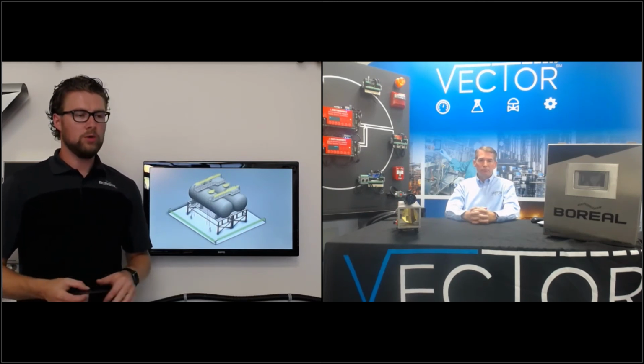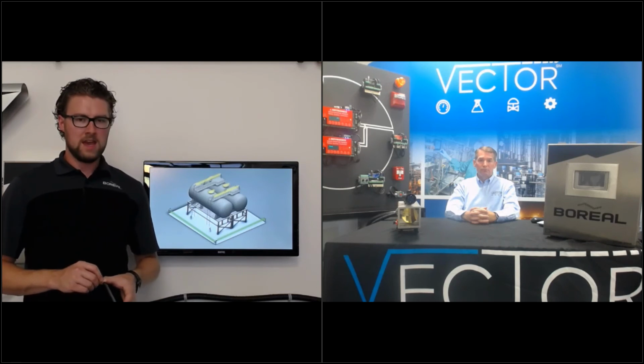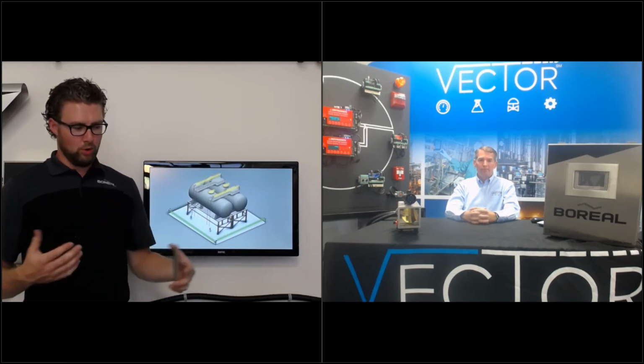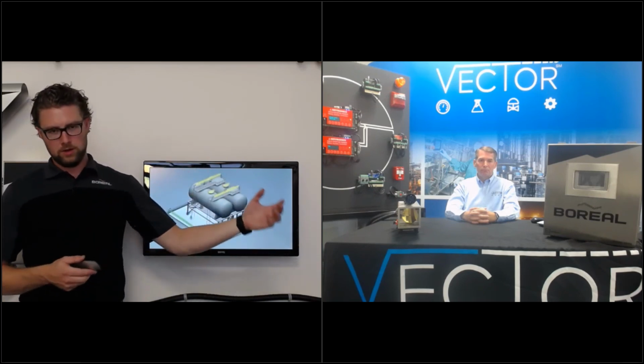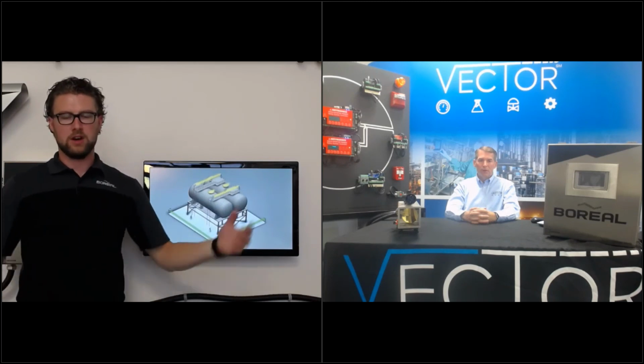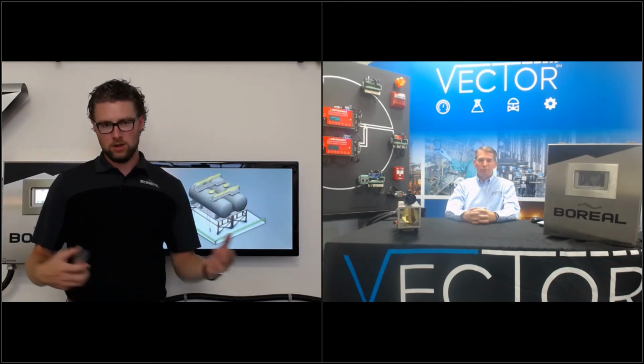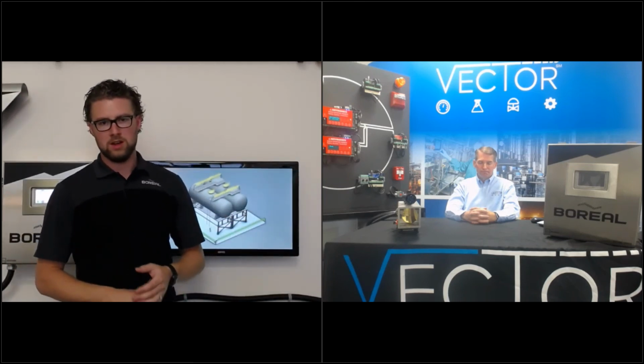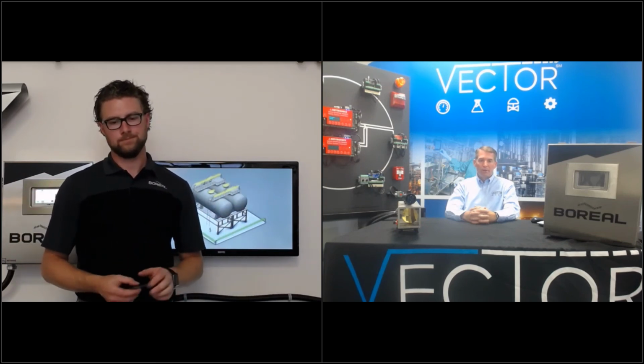Really, really good device. Just as an example, ammonia is toxic at low concentration, but is also combustible in higher concentrations. I think we've all seen the incident in the news this week in Beirut with the AN that possibly exploded there. Another important point is we can do toxic low-level concentrations of ammonia, but we also can see up to 100% ammonia as well. So we can see LEL concentrations in an open path scenario of ammonia as well. If there is interest, we can do both toxic concentrations for personnel detection, but we can also monitor for LEL concentrations of ammonia to help hopefully prevent incidents like that occurring again. Right.